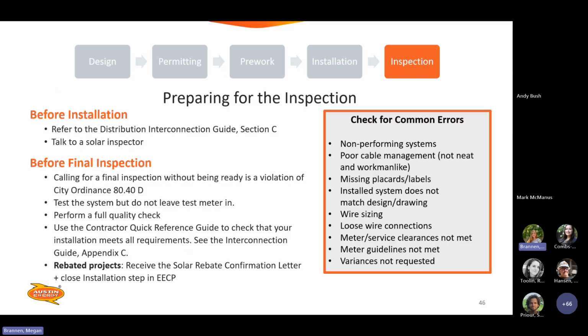Alrighty, so preparing for the inspection. Prior to installation, refer to the distribution interconnection guide, section C, or talk to a solar inspector. Again, you can do that via pre-construction meeting, or just reaching out to us at solarinspections@austinenergy.com. Our inspectors can be reached there as well. Prior to final, we want to make sure that you guys are ready for that. It is a violation of city ordinances if you're calling for finals and you're not ready. So please do just make sure that everything's buttoned up so that we can conduct a final inspection and not have to get it rescheduled or canceled or failed for any reason.